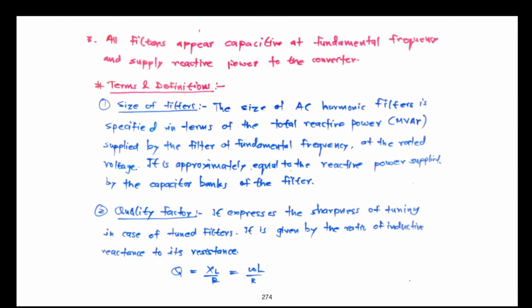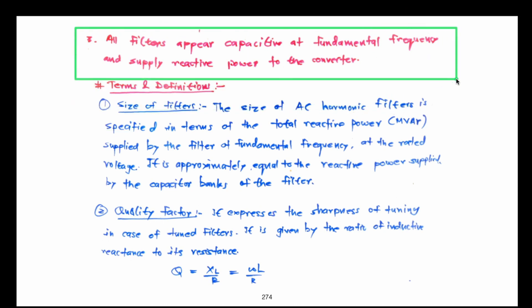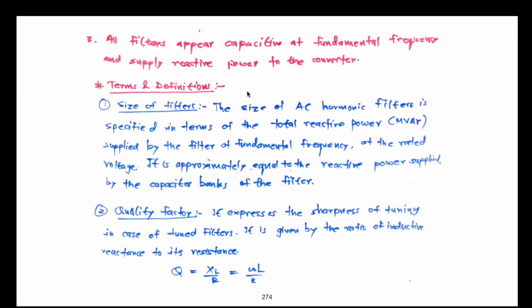The filter components are not only acting as filters, but they appear capacitive at fundamental frequency and supply reactive power to the converter. This dual purpose is very important: filters not only eliminate harmonics from the power system but are also responsible for providing the reactive power required by the converter. These are the design criteria and requirements of the filter.